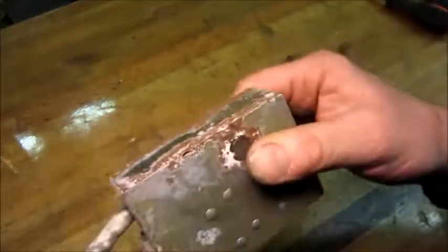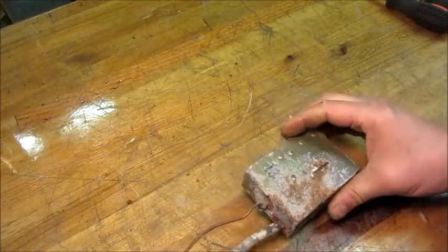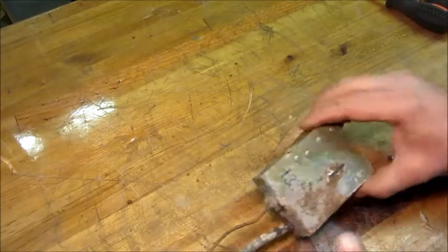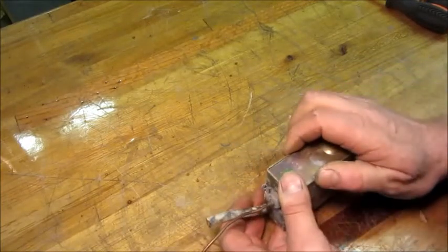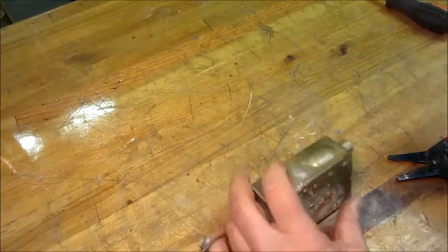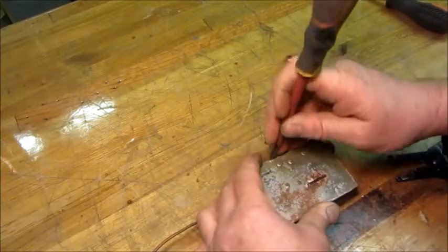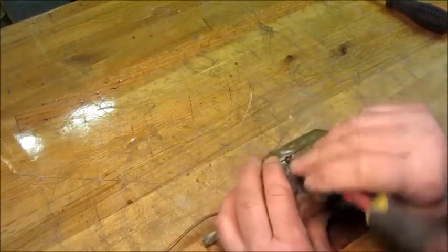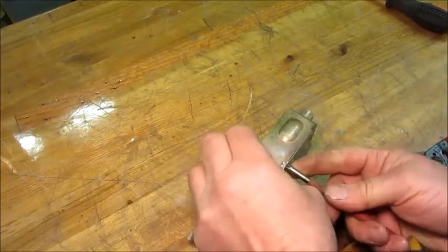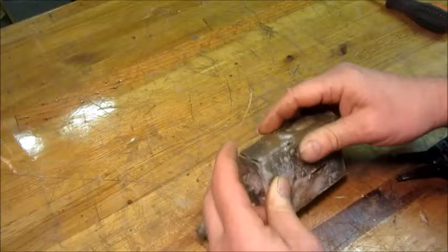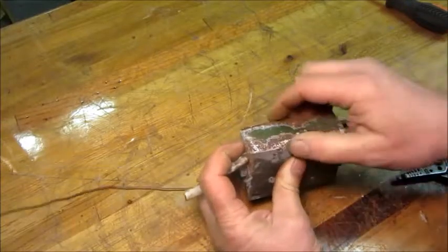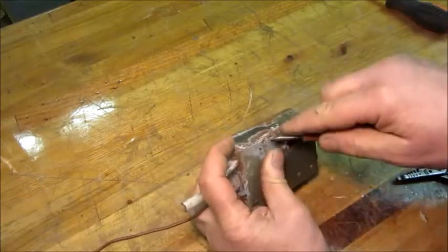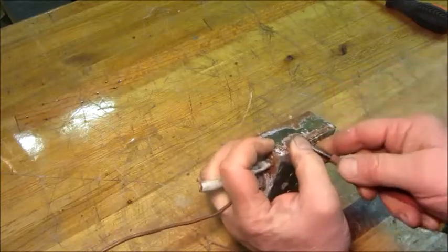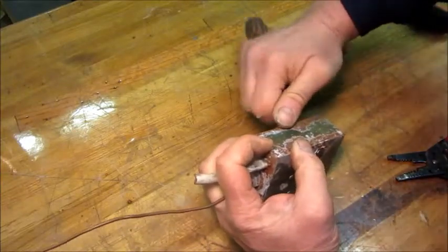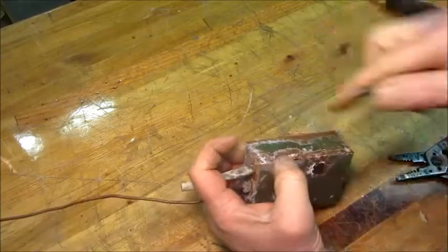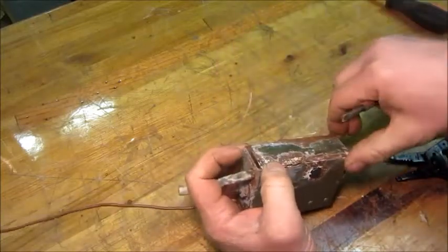Listen. I don't hear a start relay armature moving around when I shake it. So that tells me right there pretty much all I need to know about why the butcher's got a hold of the compressor wiring. It was probably not starting with this start relay because the relay stuck, and they were too dumb to try to look up a manual for the machine to understand how it's supposed to work. And so they just figured it was a compressor. Told the owner that the compressor's bad.